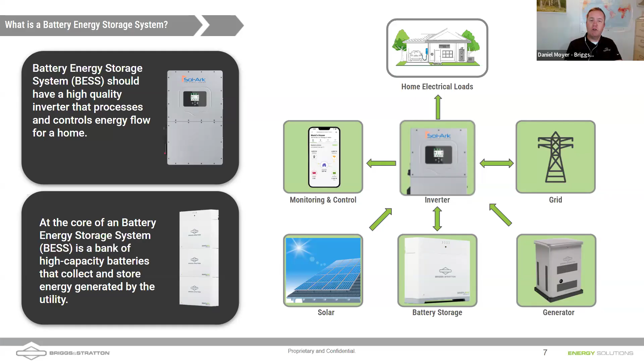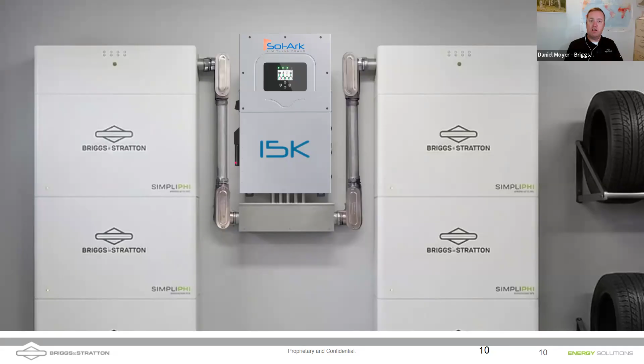So great point. One thing I'm excited to show everybody is historically the SimpliPHI 6.6 battery had a controller at the top. That's where the communication cables go, and where the power conductors go down to the inverter. That always had the 2-inch knockout on the right-hand side of the controller. So that was easy, right? If you had the inverter on the right and battery on the left, you could easily pipe it down.